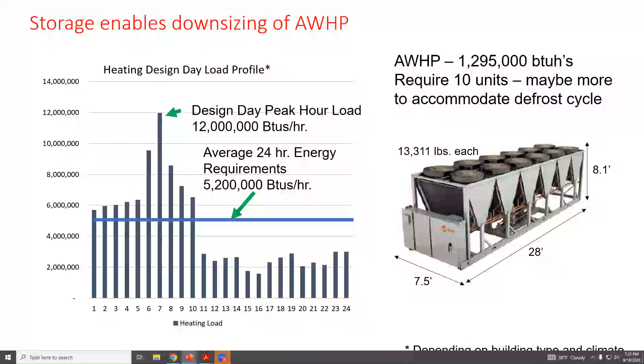Instead, as an alternate, we can size our air source along with our thermal storage tanks to provide roughly half, or 40%, of the heat needed. This doesn't mean the production side, what's actually producing the heat, drops below that 12,000 MBH, but it means where we are getting the heat from, the ambient air, can drop down. Overnight, we can melt the ice tanks via air source heat pumps, and as long as we have enough storage to account for that half of air source heating, we have enough heat source to provide to our water-to-water products to feed the rest of the building.